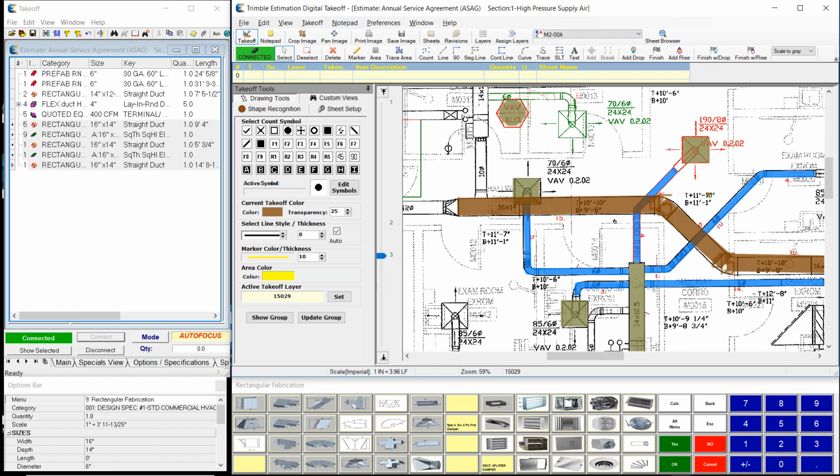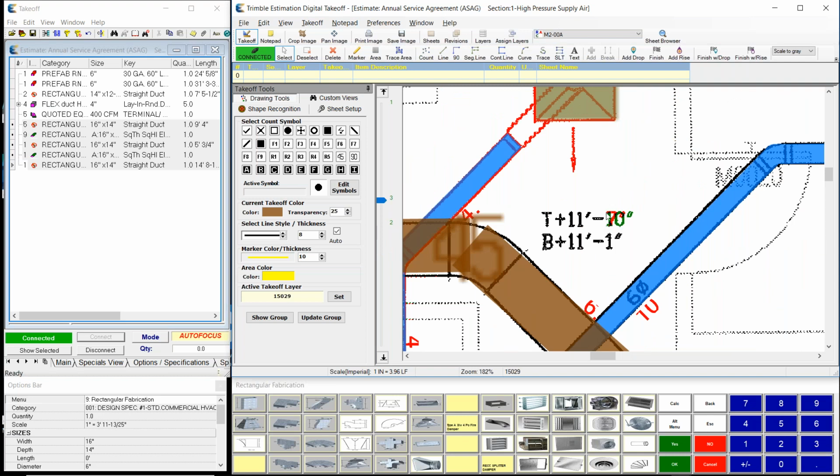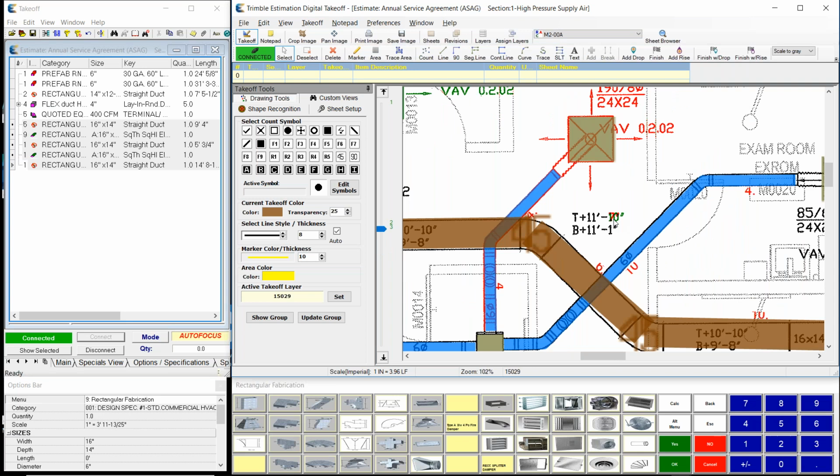And if I zoom into this area here, you can see that this VAV box is no longer there. It's in red. And this trunk coming out of here is no longer here. It is moved there. They've added one here. So a little change in differences there. One other thing, just notice real quick, was a change in size. So it went from 7 to 10. Very difficult to see that.